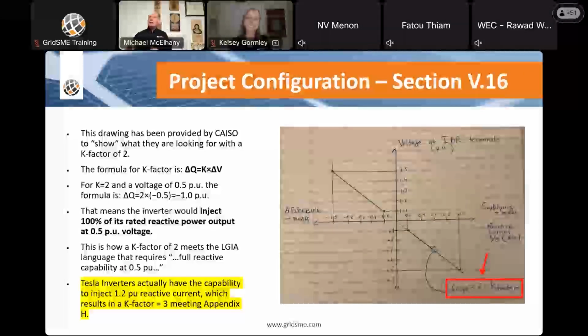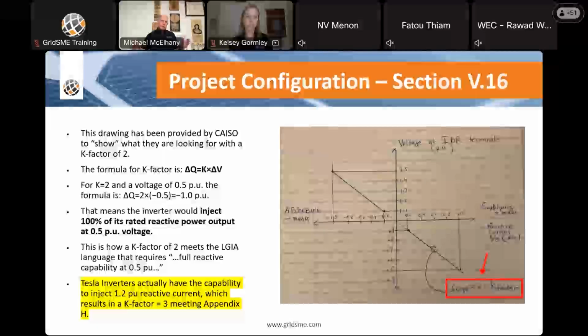But K factor is really a slope. Once you get outside the allowable range of 0.9 per unit to 1.1 per unit voltage, you need to start injecting the reactive current properly. And you have to achieve the full reactive capability at 0.5 per unit voltage or below. So you see on this chart, there's a dashed line through the middle where the power plant controller is controlling power priority, and there's reactive based on power factor and everything else. But once you get outside or below, we'll specifically talk about that.